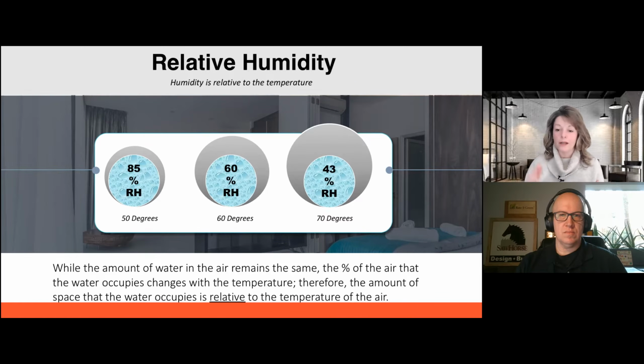And of course, filtration's a big one, but relative humidity is one where there are ranges out there. They're saying 40 to 60%. Well, we can't say relative humidity without knowing a temperature, because relative humidity is relative to the temperature. So if we look at this slide here, on the far left, we've got 50 degrees and this exact amount of water is 85% relative humidity. If we do nothing, we have the same amount of water, but just increase the temperature, that relative humidity goes down to 43%. So we need to understand what the temperature is in order to actually understand what the relative humidity is.